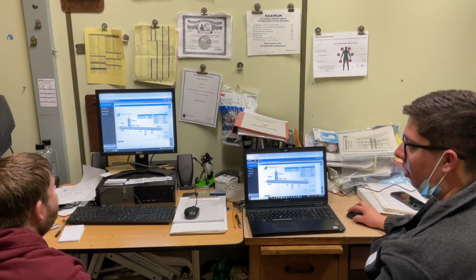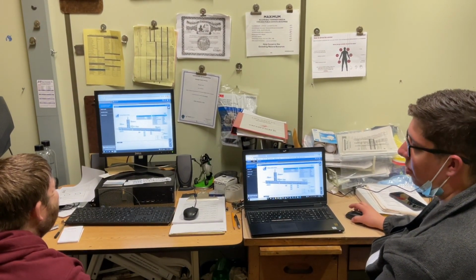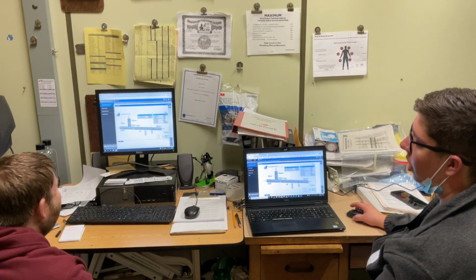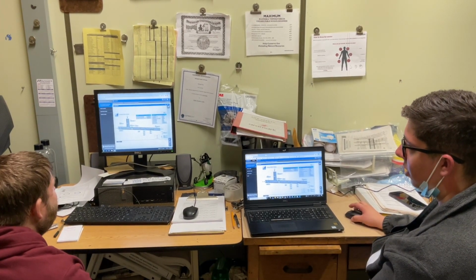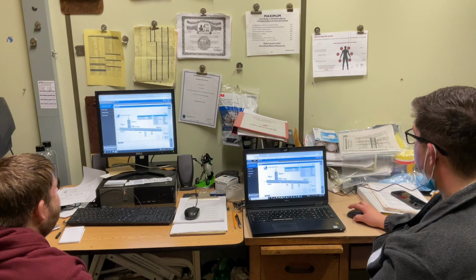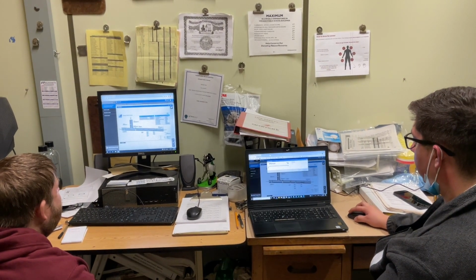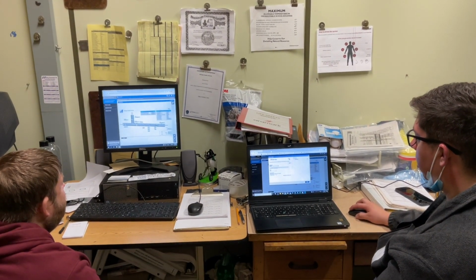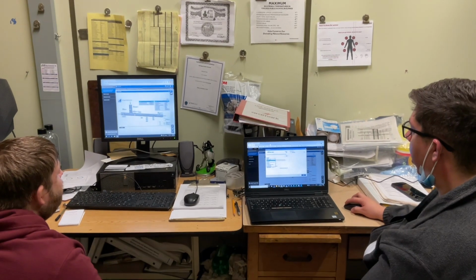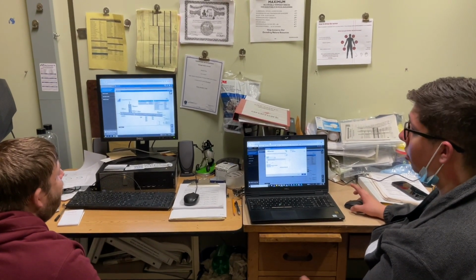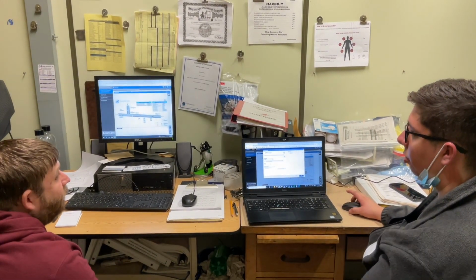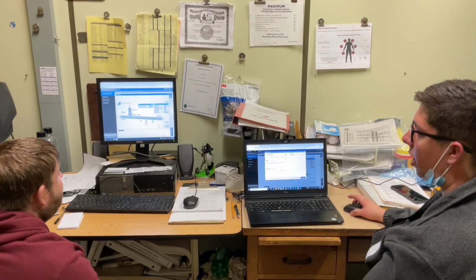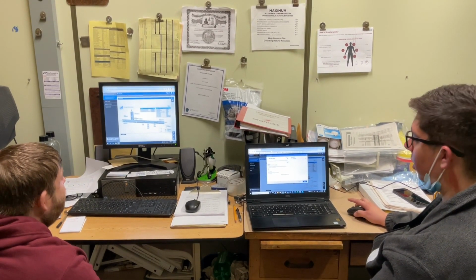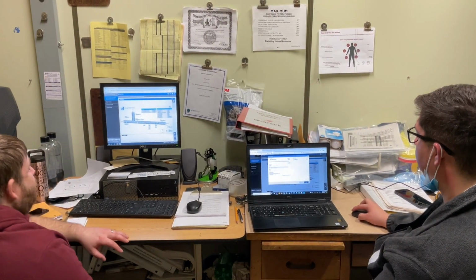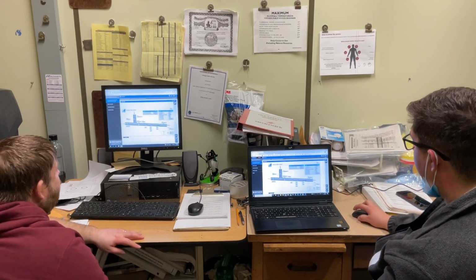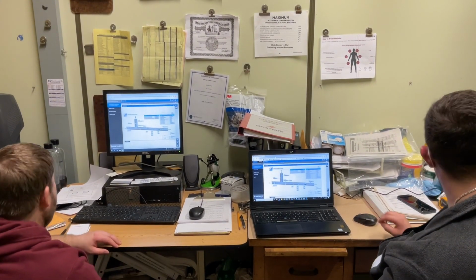Low temp reset, we've used that a couple times. If it trips out on low temp, it will not go back to normal until you toggle that. You'll just have to do an adjust. You won't have to do an override on that. And if you do an override by chance, make sure we release that, because if it stays on reset, it won't go back to normal. You need that to be off to be in a normal state. Cooling enable, reheat enable.